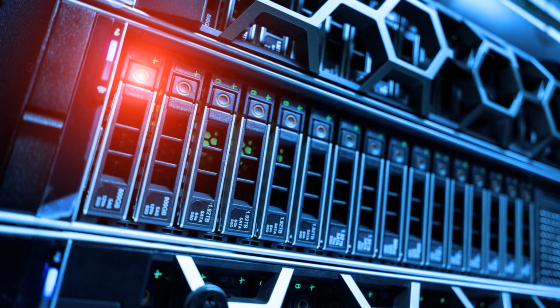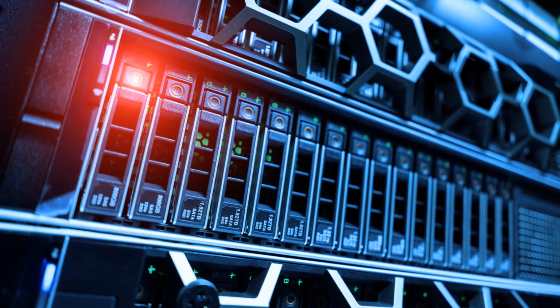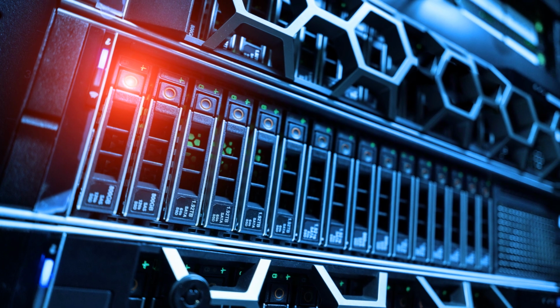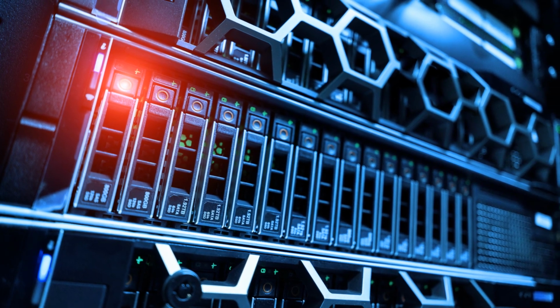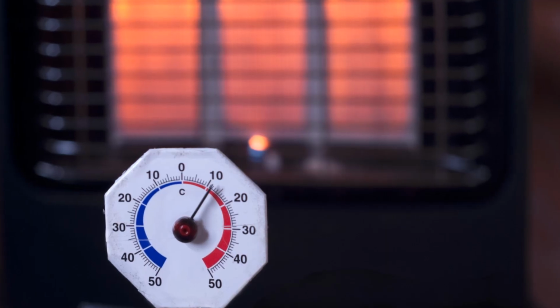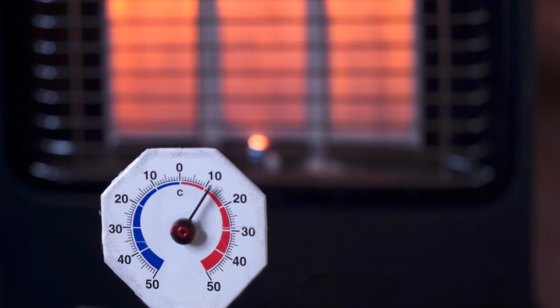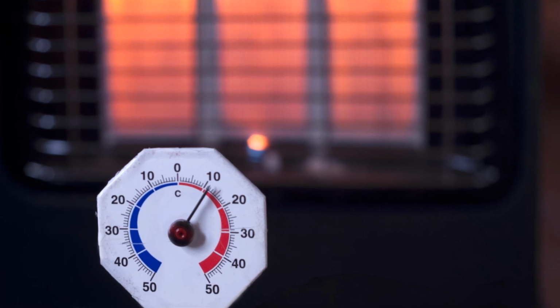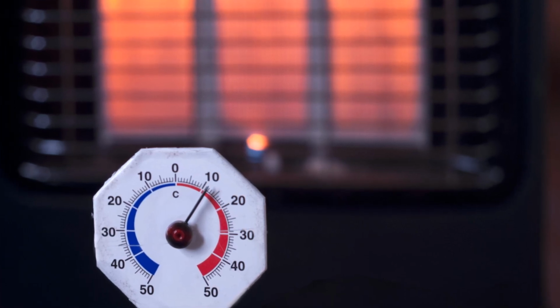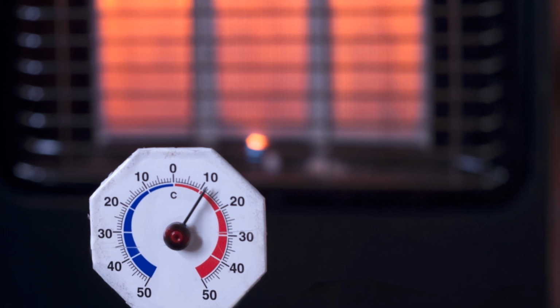ASHRAE provides guidelines for server inlet temperature: recommended lower bound 18 degrees Celsius, upper bound 27 degrees Celsius, running at the high end 26 or 27 degrees Celsius to save energy is tempting, but leaves very little safety margin. A small cooling failure can push you into the danger zone.